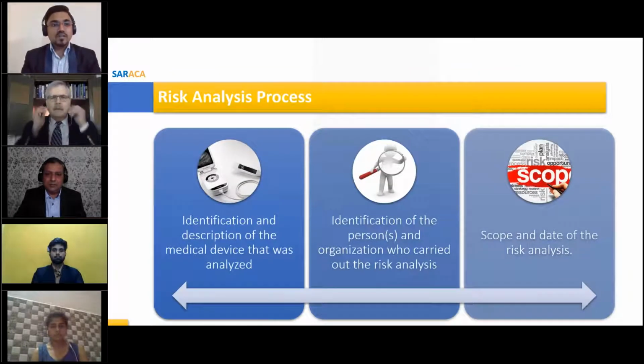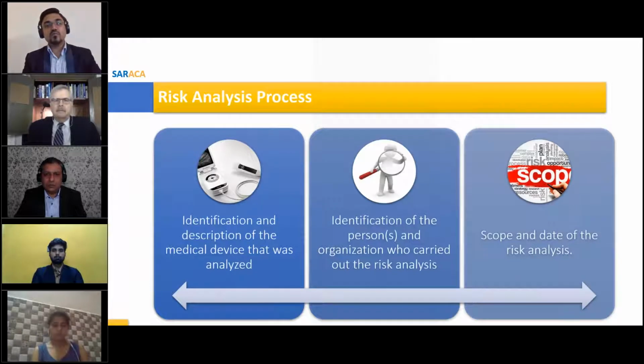So, the risk analysis process. I'm going to tell you the process you can follow to do a risk analysis. You need to identify and describe the medical device that is analyzed. So what device are you going to do the risk assessment on? You need to identify it and do the device description. This device description is a very lengthy process in our medical device industry. So first you need to finalize your device description in a proper manner. Then only can you describe your device in a proper sequence, meaning all your technology or your science background. So first you need to do that.